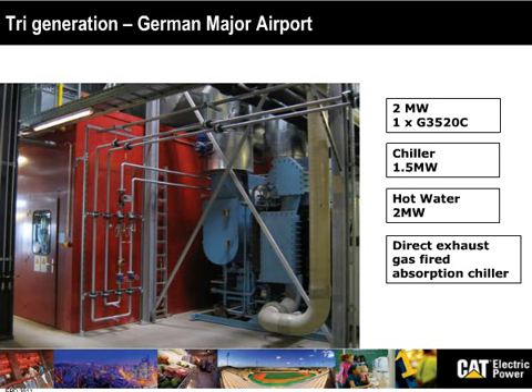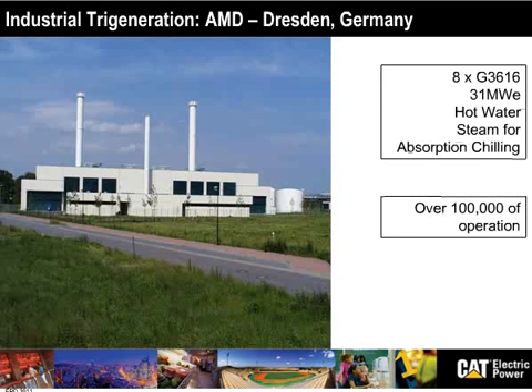Absorption chillers not only for airports. Here is an industrial application that's been ongoing for over 10 years. It's a 31 megawatt cogen producing everything: hot water, steam, and absorption chiller. This is a chip manufacturer based in Germany. So we can do hot water, steam, fresh water. We can do CO2. We can do chilled water. So what else can we do?